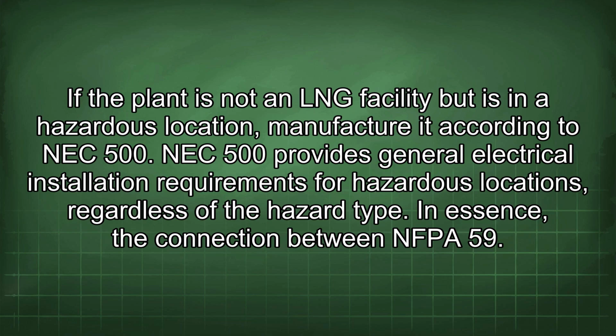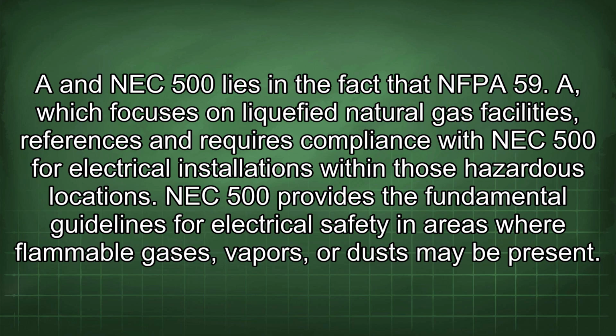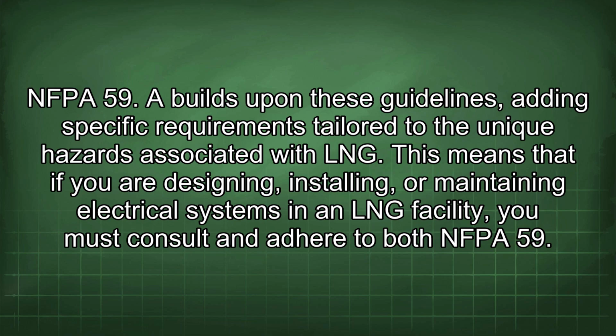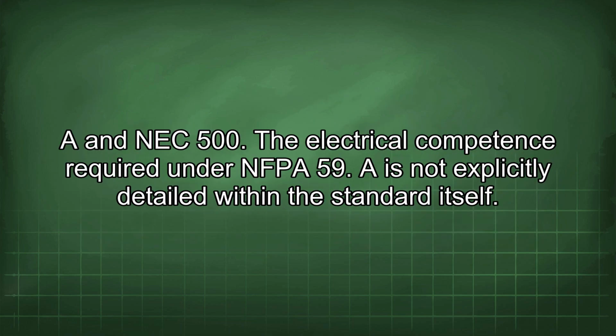In essence, the connection between NFPA 59A and NEC 500 lies in the fact that NFPA 59A, which focuses on liquefied natural gas facilities, references and requires compliance with NEC 500 for electrical installations within those hazardous locations. NEC 500 provides the fundamental guidelines for electrical safety in areas where flammable gases, vapors, or dust may be present. NFPA 59A builds upon these guidelines, adding specific requirements tailored to the unique hazards associated with LNG. This means that if you are designing, installing, or maintaining electrical systems in an LNG facility, you must consult and adhere to both NFPA 59A and NEC 500.